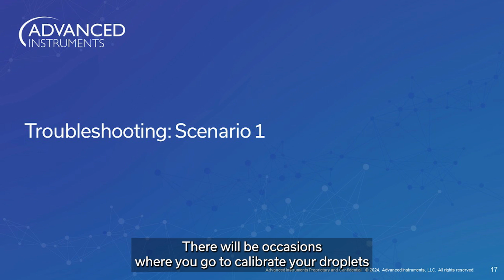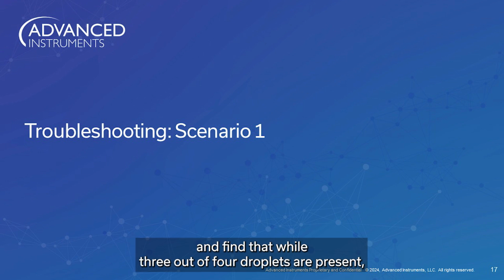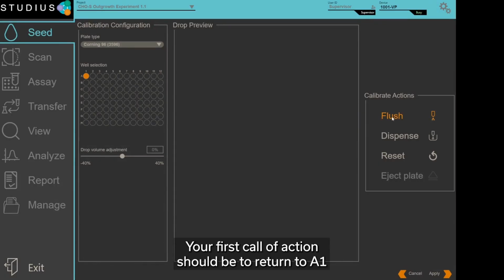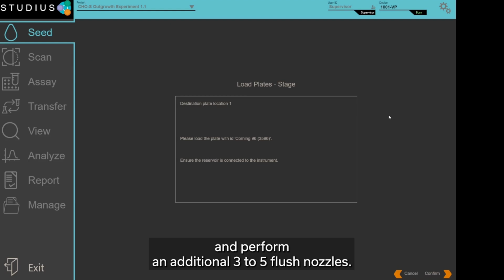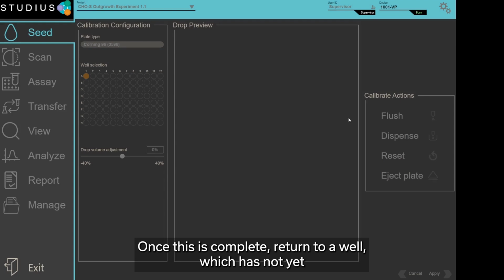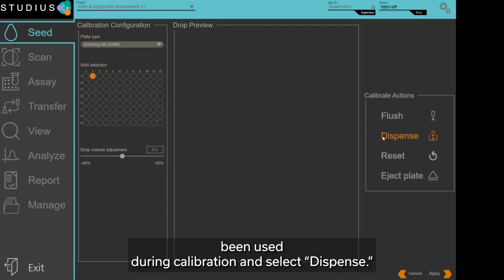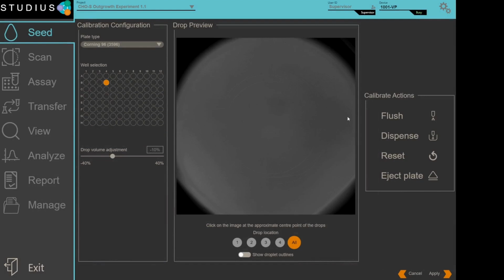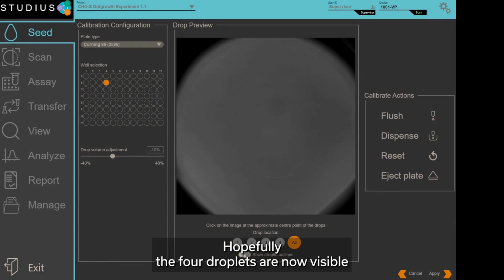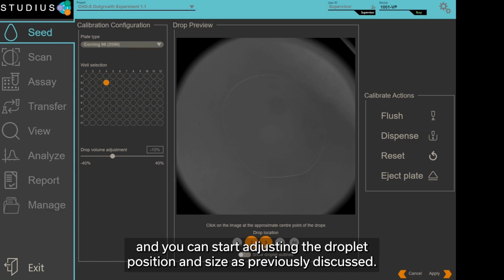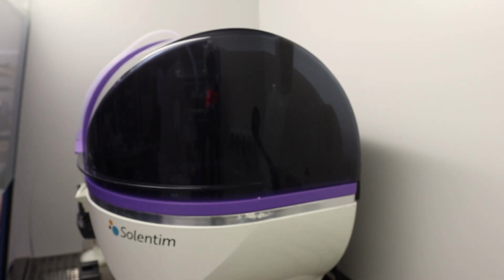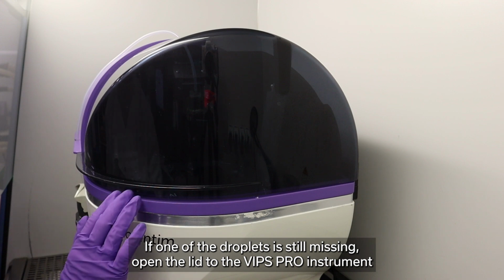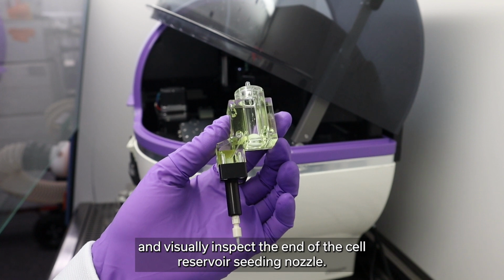There will be occasions where you go to calibrate your droplets and find that while 3 out of 4 droplets are present, one of them is missing. Your first course of action should be to return to A1 and perform an additional 3 to 5 flush nozzles. Once this is complete, return to a well which has not yet been used during calibration and select Dispense. Hopefully, the 4 droplets are now visible and you can start adjusting the droplet position and size as previously discussed. If one of the droplets is still missing, open the lid to the VIPS Pro instrument and visually inspect the end of the cell reservoir's seeding nozzle.